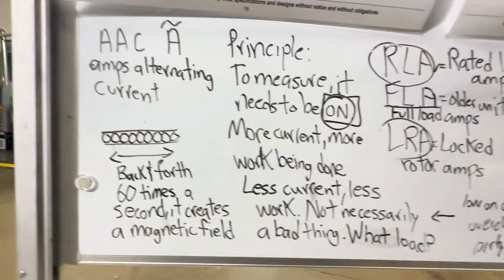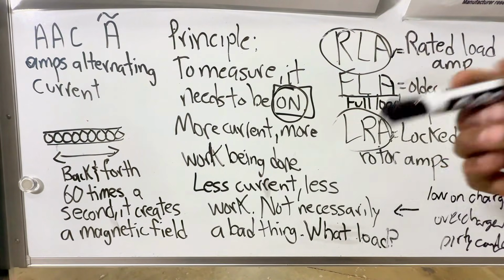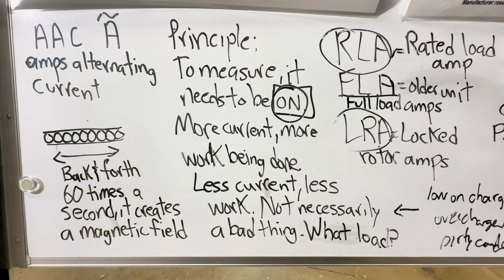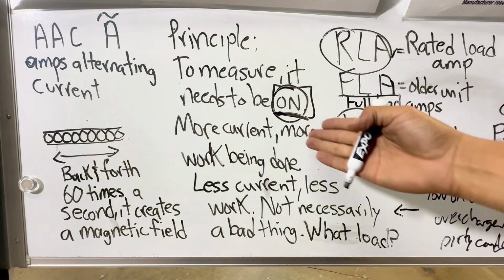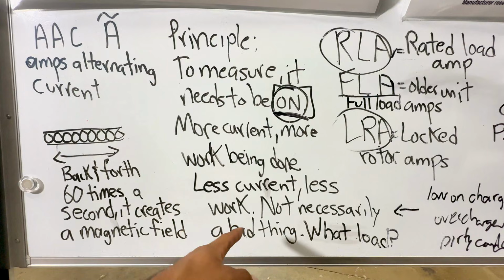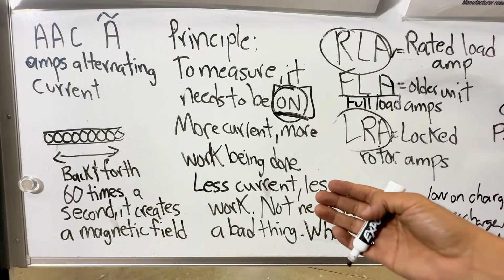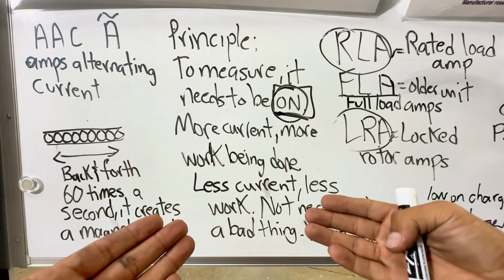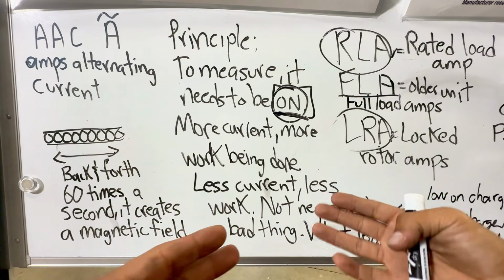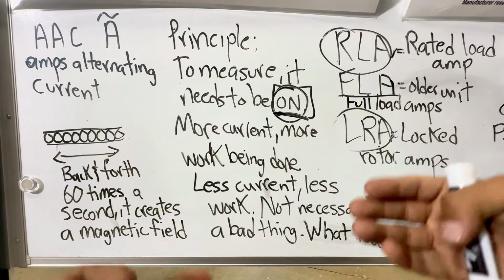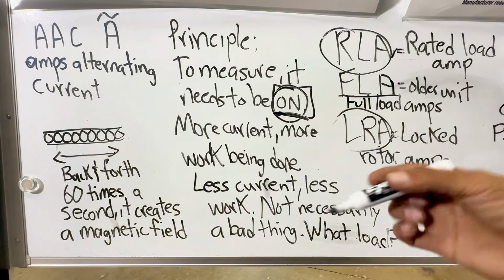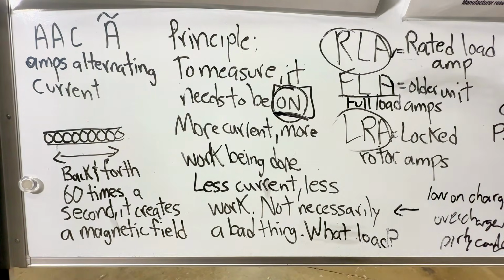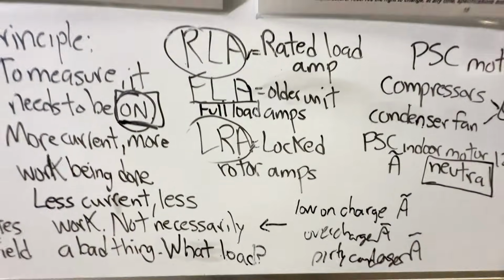So the principle here, this is important to understand: whatever you're trying to measure current on, it needs to be on. I cannot emphasize that enough. It needs to be on. And of course, more current, more work is being done. Less current, less work is being done. But keep in mind, you might have a load like a compressor that's going to pull a lot of current. But when you compare that to a condenser fan motor, it's going to pull a lot less current. So just because it's pulling less current, it doesn't necessarily mean that something's wrong with it. It's just not doing a lot of work. Now, of course, if a compressor is pulling a lot less current than usual, then that can tell you there's something else going on. And these are some of the terms that you want to have in mind.